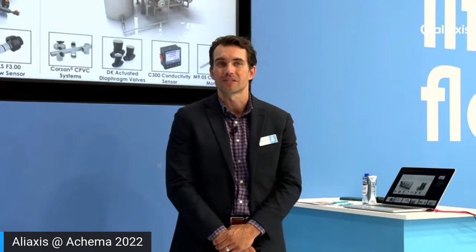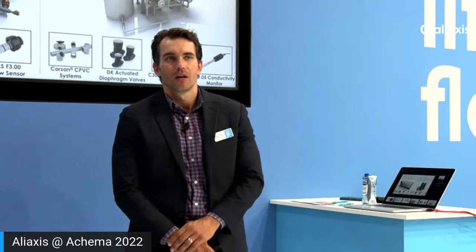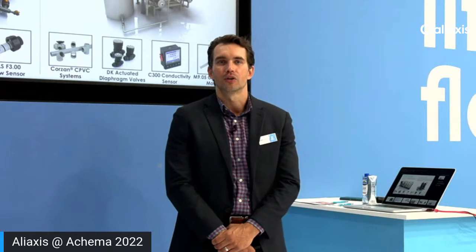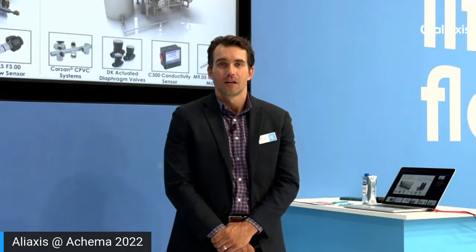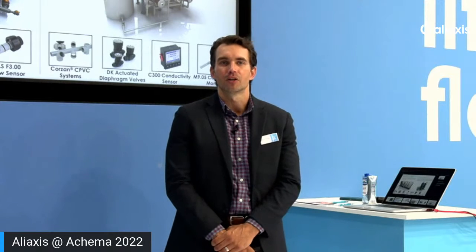It may be possible to use materials like CPVC, chlorinated polyvinyl chloride, which is capable of operating up to 95 degrees Celsius. So we may find that in many of these applications, there are a lot of different material and system choices. This is where a good manufacturer is going to be able to support you and provide guidance based on your project and technical requirements to make the optimal piping system choice for your specific application. At a minimum, a good manufacturer is going to be able to provide this support.